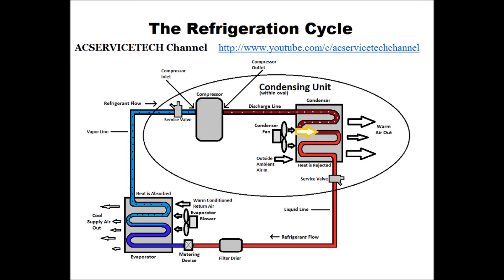It comes from the saturated state in the middle of the condenser coil and continues to reject heat as a complete liquid until it comes out of the condenser coil. Then it comes down in the picture, makes a left, and goes through the filter dryer. The filter dryer is there to absorb any moisture in the system — it has a fixed capacity and that's it.